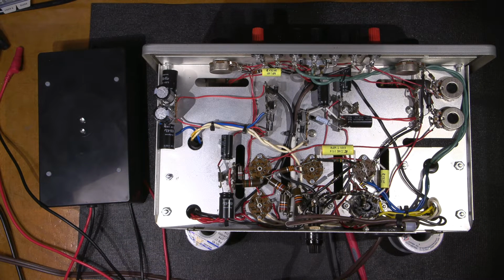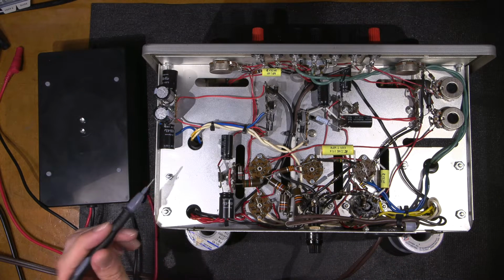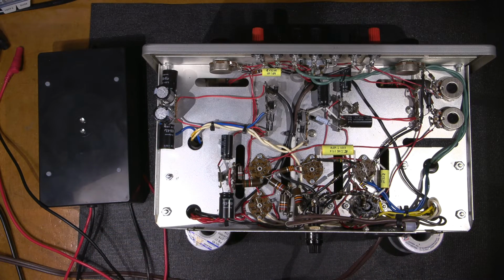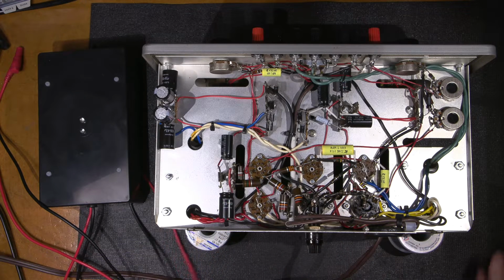And depending on the situation and the piece of test gear, a lot of chassis will sit isolated from the circuitry, so always keep that in mind. Never think that you can use the chassis and run across to all the capacitors. Always go across the capacitors with a discharge device. You never want to rely on the chassis to do that. I'll give you an example again.